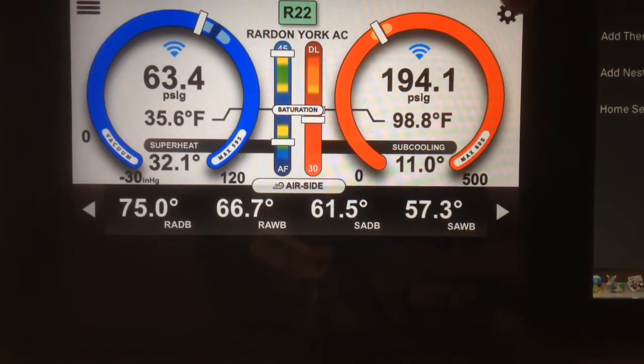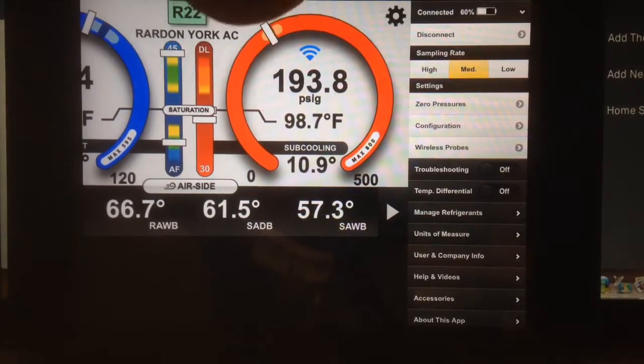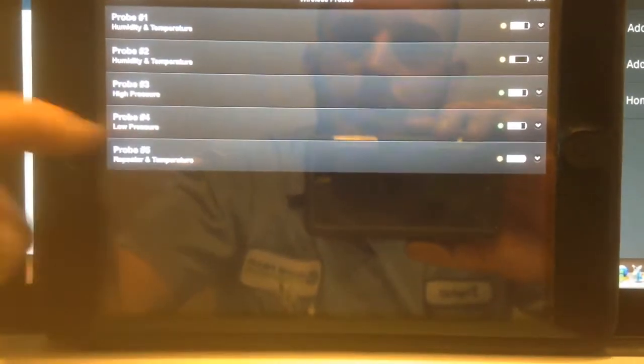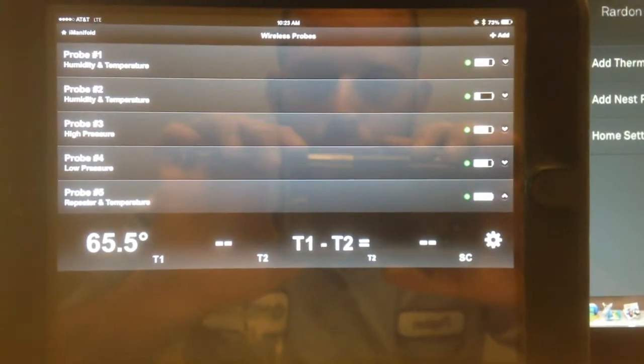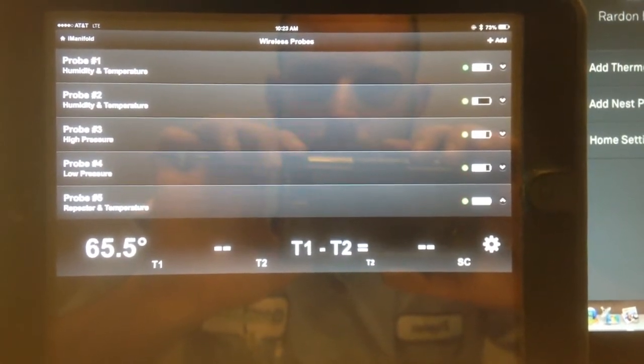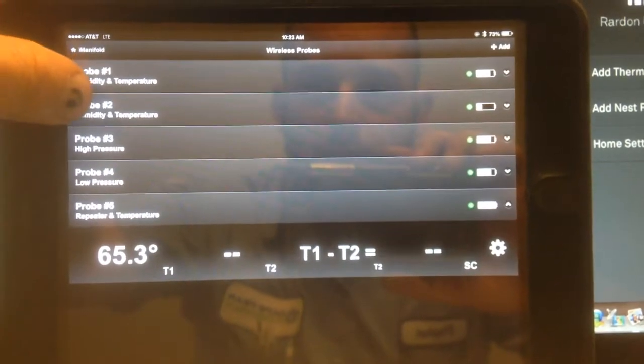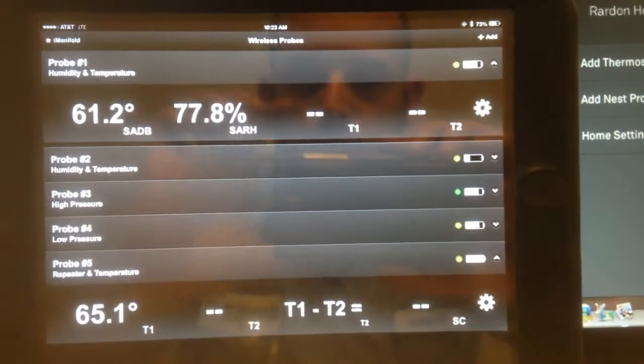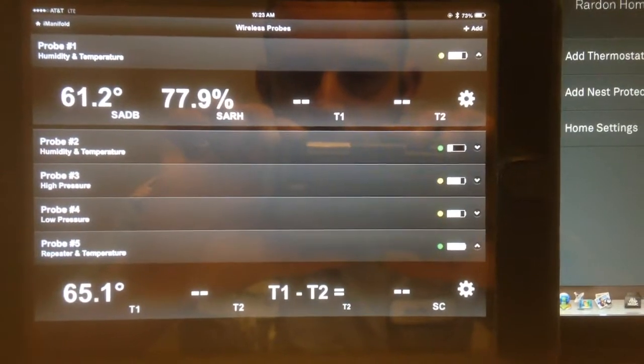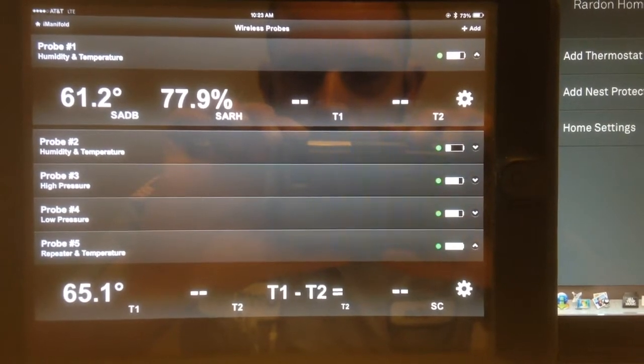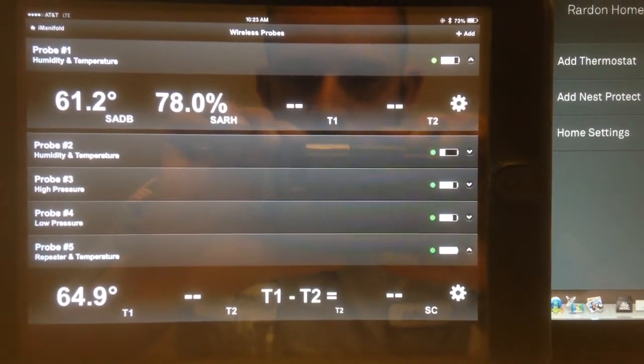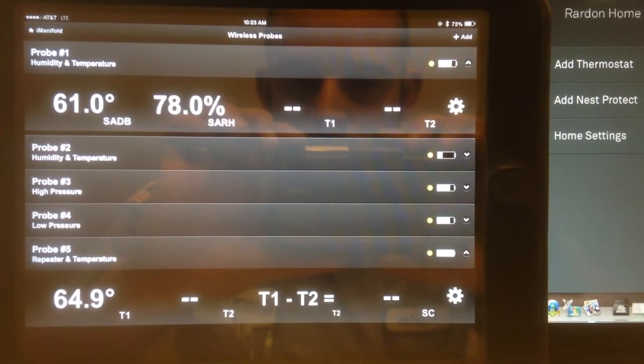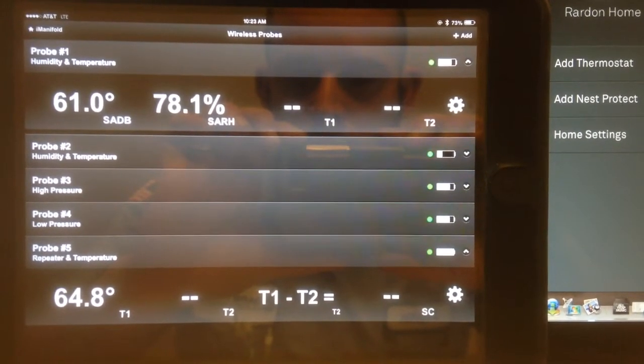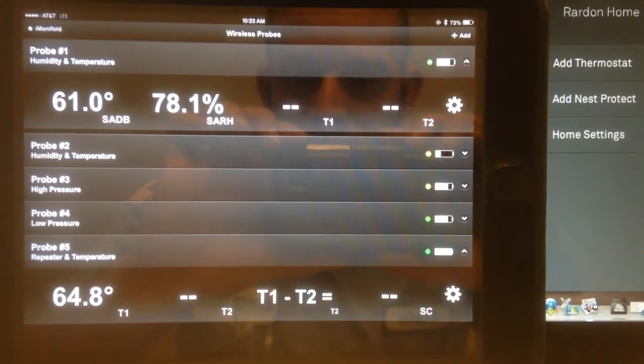We're going to go back over to wireless probes and look at that information. Since we did have it set up in the airstream off of that register, we are getting a temperature off of that. And just for fun, you can see that I'm apparently losing about 4 degrees of delta T from the distribution box for the second floor over to the register air output itself.